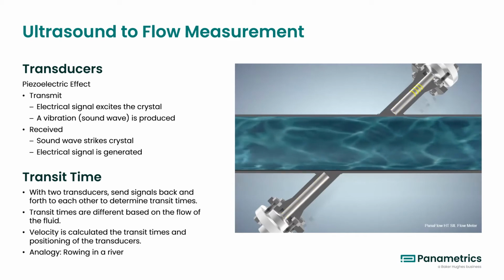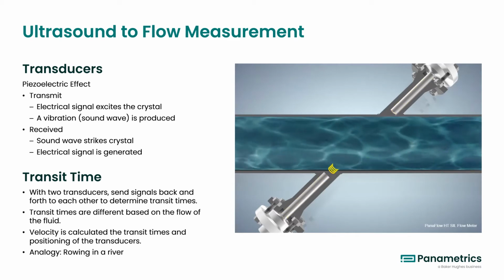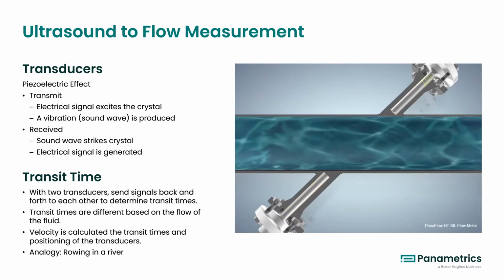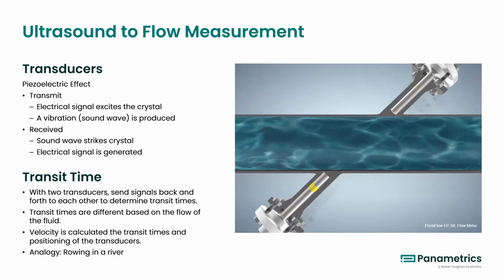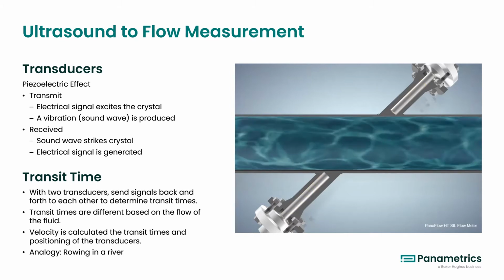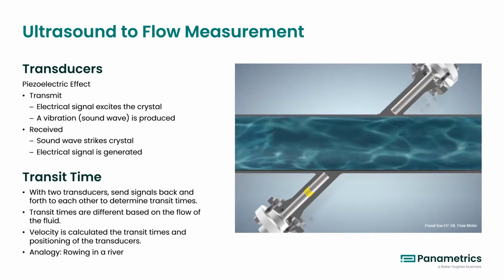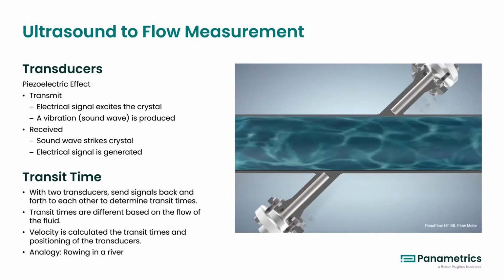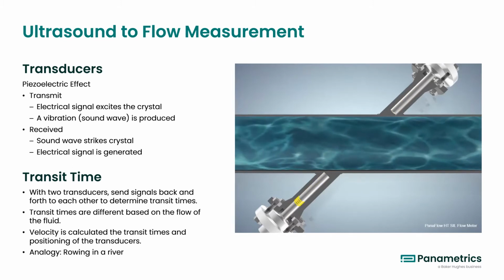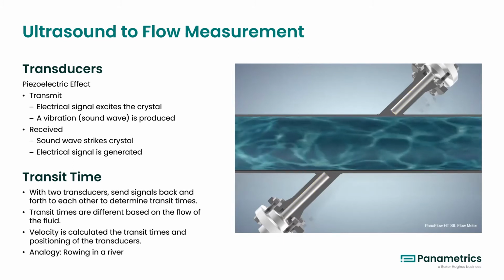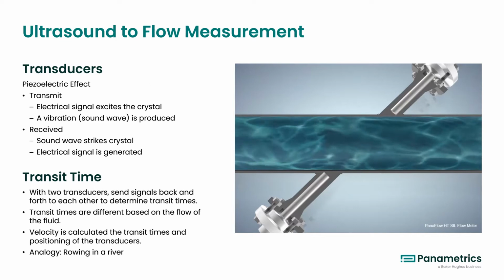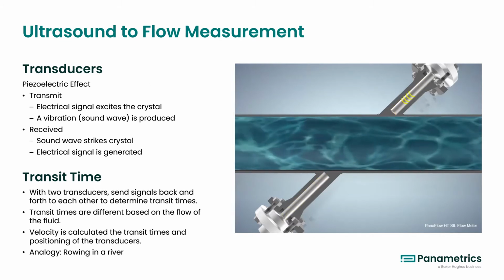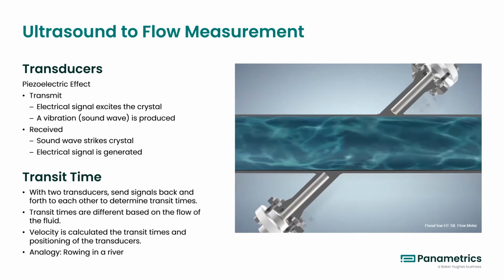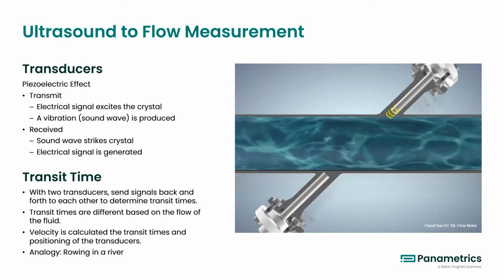There are three main methods of ultrasonic flow measurement. Transit time is the most common method of measuring flow with an ultrasonic flow meter. I will not be discussing Doppler or correlation tagging principles. With a transit time flow meter, two transducers are mounted on opposite sides at an angle so that one transducer is upstream of the flow and the other transducer is downstream of the flow. The transducers act as a pair and both transmit and receive ultrasonic signals.